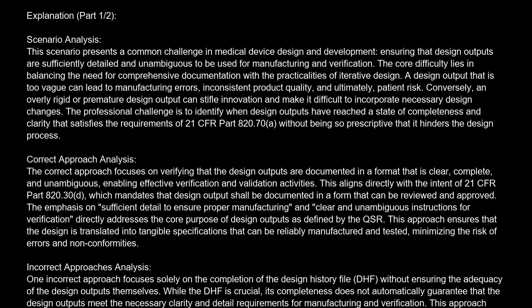The core difficulty lies in balancing the need for comprehensive documentation with the practicalities of iterative design. A design output that is too vague can lead to manufacturing errors, inconsistent product quality, and ultimately, patient risk. Conversely, an overly rigid or premature design output can stifle innovation and make it difficult to incorporate necessary design changes. The professional challenge is to identify when design outputs have reached a state of completeness and clarity that satisfies the requirements of 21 CFR Part 820.30(d), without being so prescriptive that it hinders the design process.